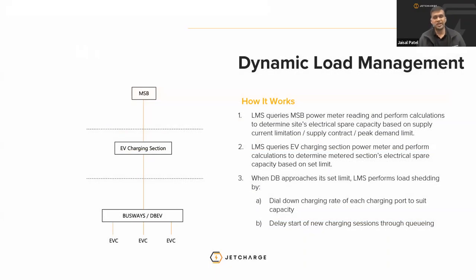So this is typically how a dynamic load management system works. I've used one of our own in-house load management systems as an example of how it uses the information it gets to work. A load management system will query the main switchboard's power meter reading or reference point and perform a calculation to determine the site's electrical spare capacity based on supply current limitations, supply contracts, or peak demand limits. There would be a secondary power meter on the EV charging section, whether it's a metered section to a supply or whether it's a distribution board feeding the chargers. The LMS will query that section and perform calculations to determine whether the metered section's spare capacity is available based on that set limit. When the distribution board approaches its set limit, the load management system performs load shedding by dialing down the charging rate of each charging port to suit the capacity and delay the start of any new charge sessions through queuing until there is available capacity to restart charging.